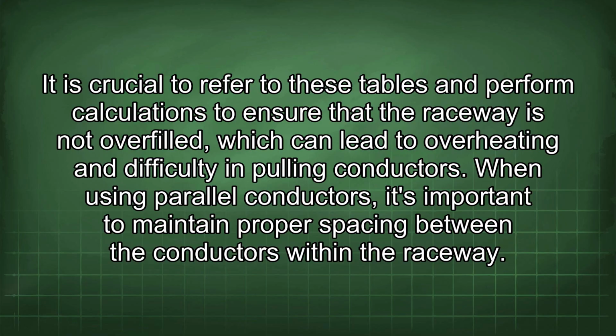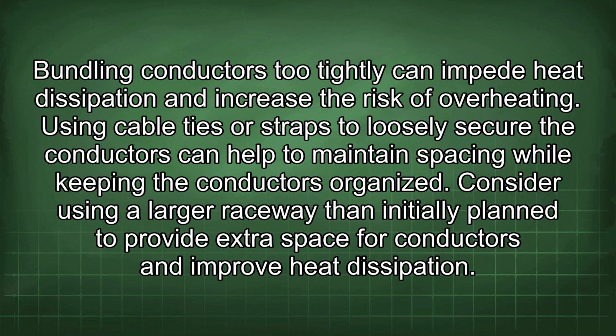When using parallel conductors, it's important to maintain proper spacing between the conductors within the raceway. Packing conductors too tightly can impede heat dissipation and increase the risk of overheating. Using cable ties or straps to loosely secure the conductors can help to maintain spacing while keeping the conductors organized.